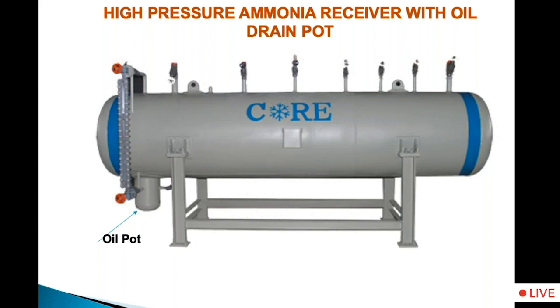Why am I saying this? Kindly remember that liquid is non-expandable or non-contractable. If you fill up the entire receiver with liquid ammonia, when the ambient temperature goes up, the liquid will tend to expand. And if there is no space provided in the receiver for expansion, the vessel will burst. Therefore, the maximum allowable quantity to be stored is 75, 80, maximum 85% when the entire system is pumped down. This is very, very important.